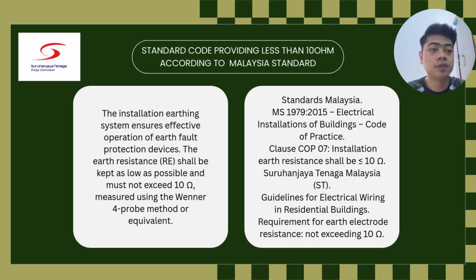Okay, for the standard code, providing less than 10 ohm according to Malaysia standard. First, the installation earthing system ensures effective operation of the earth fault protection device. The earth resistance RE shall be kept as low as possible and must not exceed 10 ohm. It is measured using the Wenner four-probe method or equivalent. Okay, for the standard measure, MS1979:2015 Electrical Installations of Buildings Code of Practice, installation earth resistance shall be less than 10 ohm. Suruhanjaya Tenaga Malaysia (ST) guidelines for electrical wiring in residential buildings require earth electrode resistance not exceeding 10 ohm.